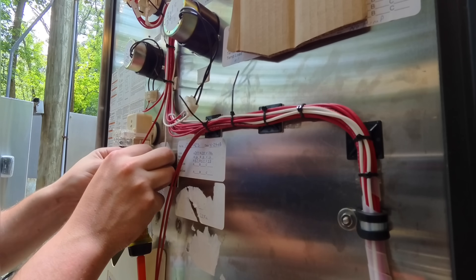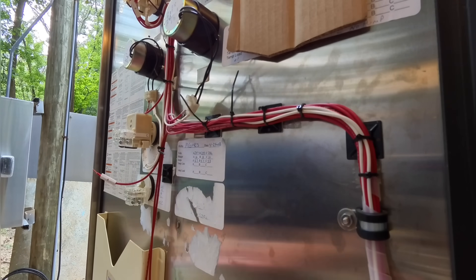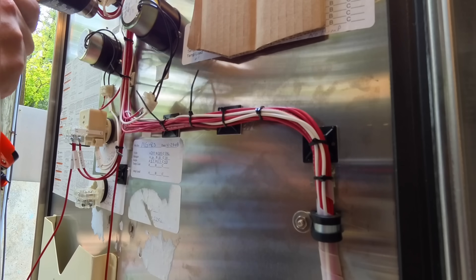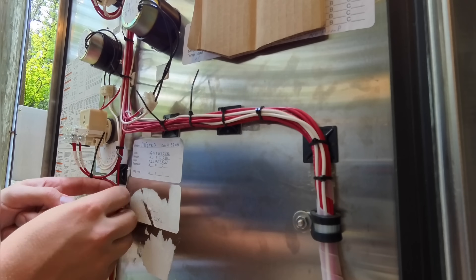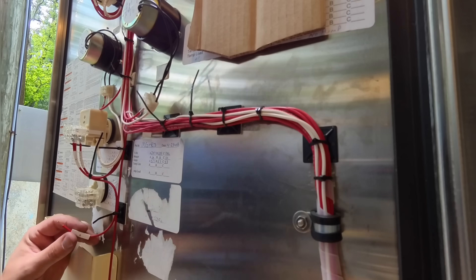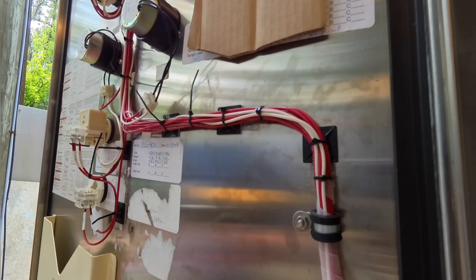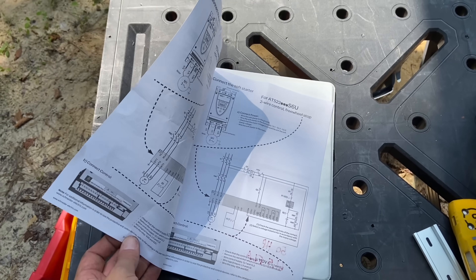But they are the devil we know, and for now I'm just going to make the best of them. I only have to run two wires to this door because I already have a neutral and a hot on the door associated with this pump's control transformer. You don't want to make the mistake of just grabbing any hot because there's two control transformers in this cabinet — those are not the same hots. So all we really needed was two wires back: one for the soft start reset and one for the fault light.